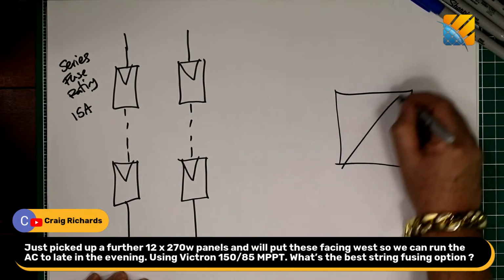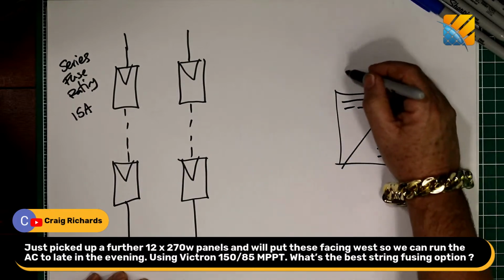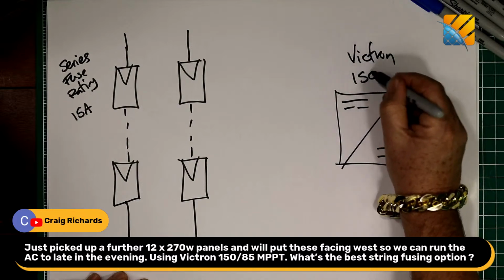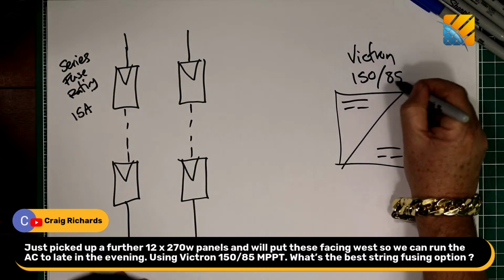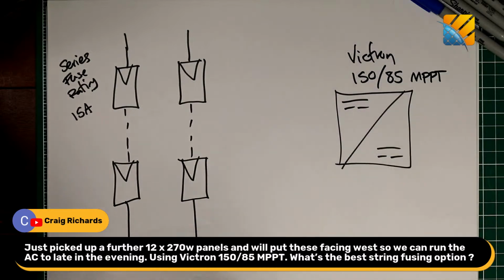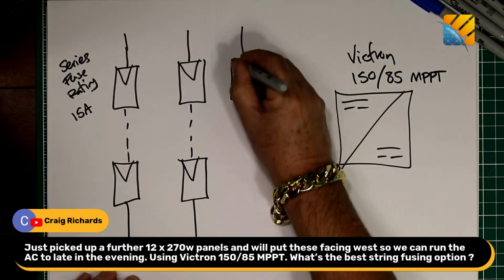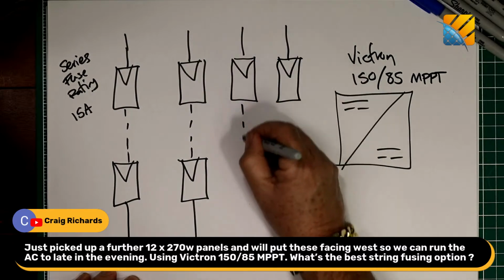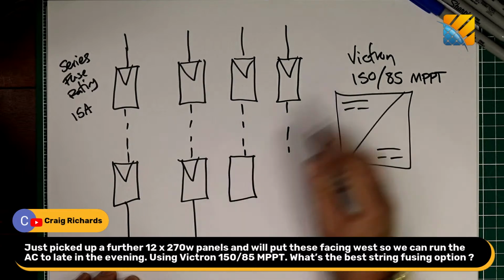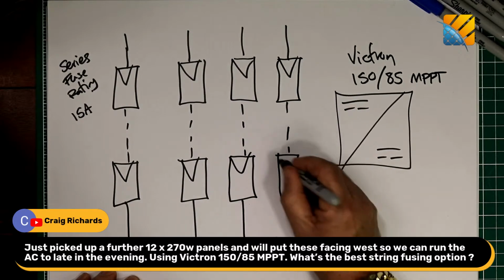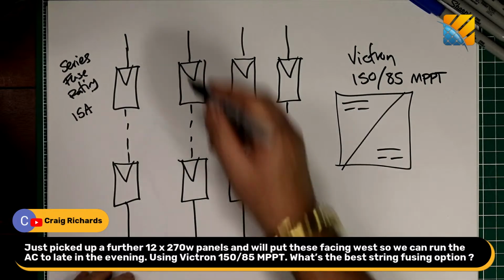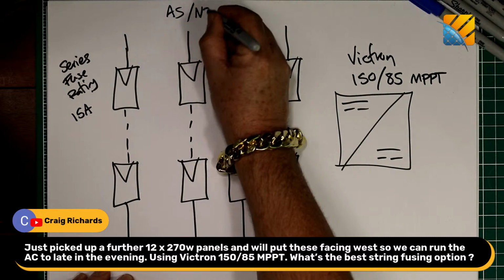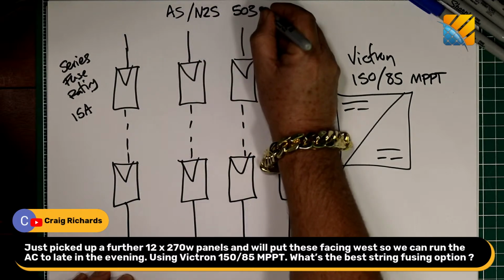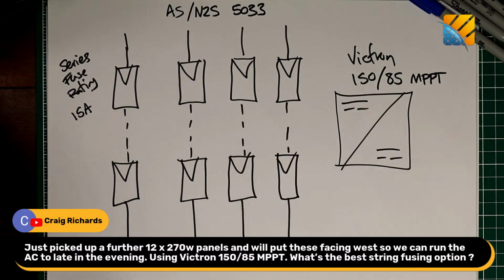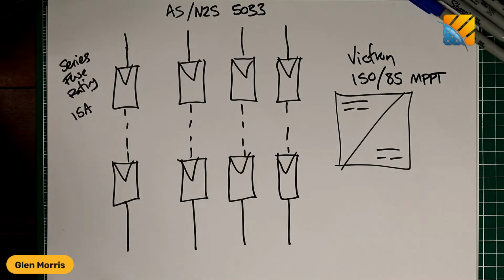So if we put your Victron MPPT over here, the symbol for a DC-DC converter, that's our Victron 150/85 amp MPPT. And what we're doing here is connecting up, and I'm going to draw those extra 2 strings really quickly. By the way, this applies to on-grid systems as well. I'm drawing an MPPT here, but it might have been an inverter. The requirements I'm drawing come straight out of the standard AS/NZS 5033, which is just being updated at the moment, so what I'm telling you now might change by the end of the year. I'll take your question off the screen so we can see all of my drawing.